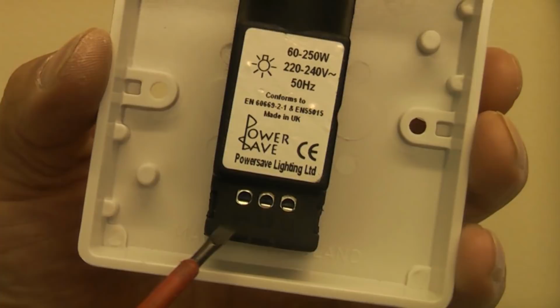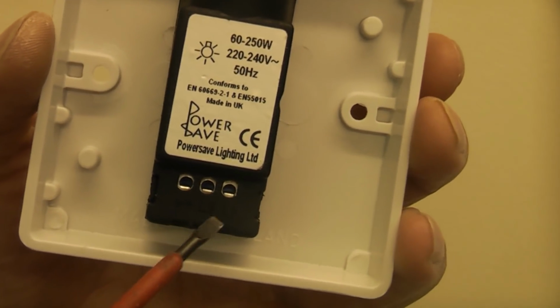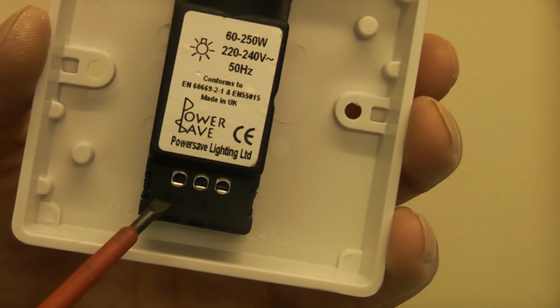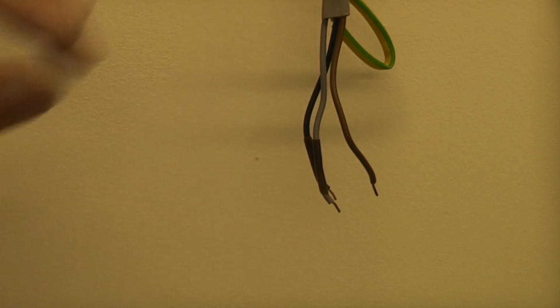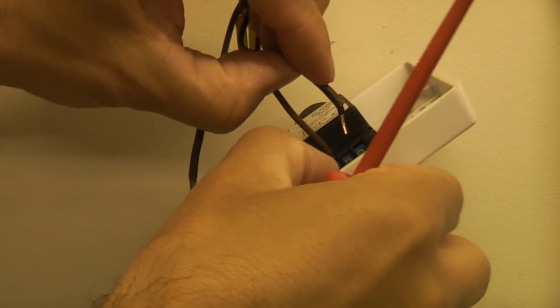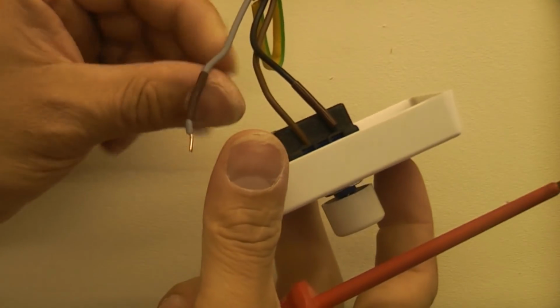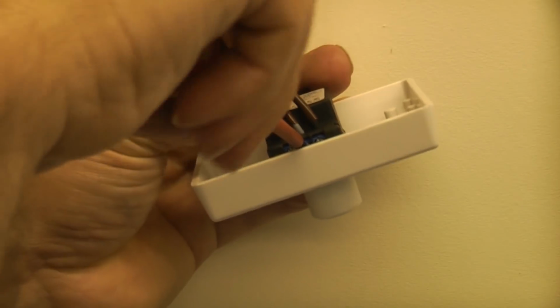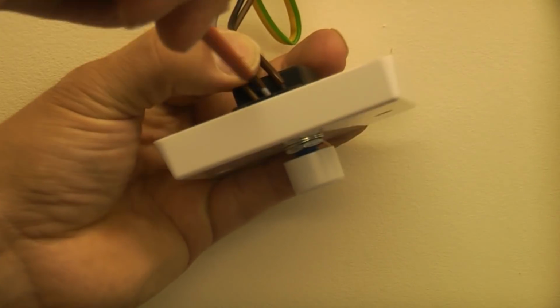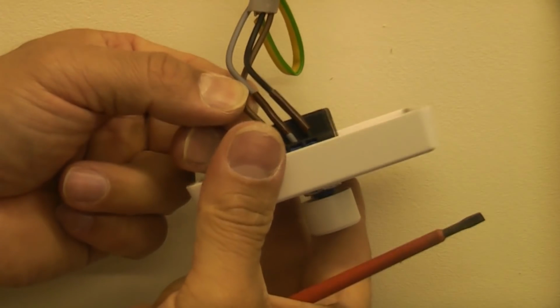The new dimmer switch has slightly different symbols. It has that squiggly line with an arrow through, an L2 and an L1. The squiggly line with the arrow through is the common terminal. So we're now going to put the brown into the common terminal. The black wire into L1. And then the grey wire into L2.